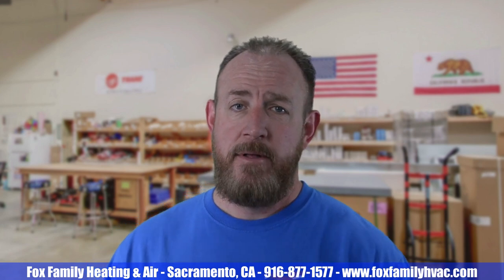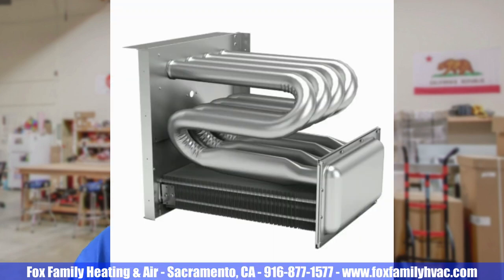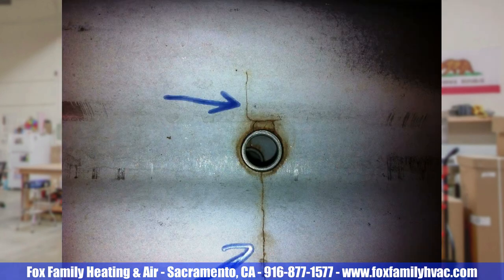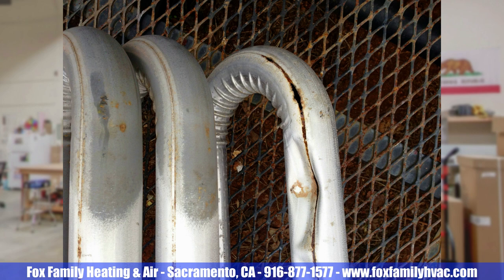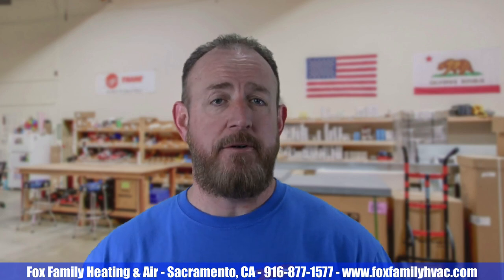The reason why every good technician does this is to make sure that the furnace is safely operating to factory specs. The manufacturer would never send out a cracked heat exchanger. So how do they fail? Operating a furnace in any one of these conditions can cause a heat exchanger to fail because it puts a lot of stress in the form of expansion and contraction over several years. Cracks and breaks will form over time because of the constant bending of the metal.